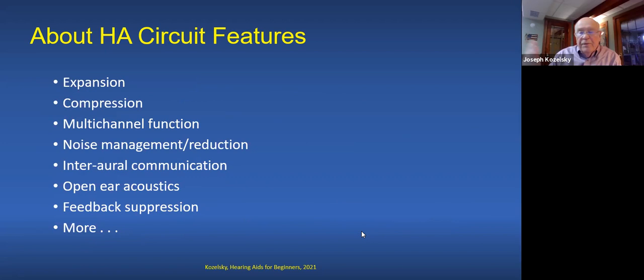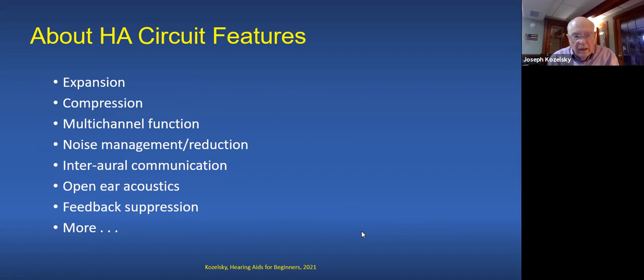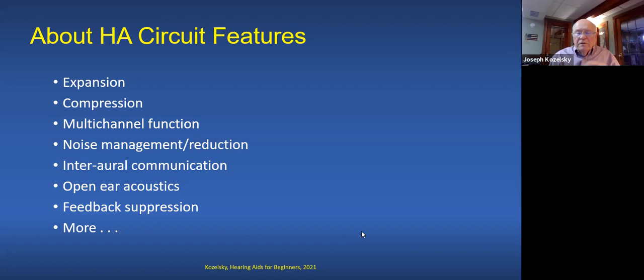There are circuit features including expansion, compression, multi-channels, noise management, and inter-aural communication. If there's noise on one side, it'll turn that down and focus on the other side where the signal is. And most modern hearing aids are open-ear — not plugging up the ear like older designs. They also have feedback suppression circuits, so they don't whistle and squeal like they used to. Some power hearing aids may still have that problem, but it's not like it was.